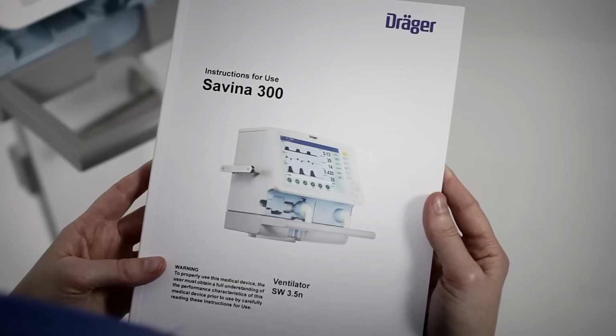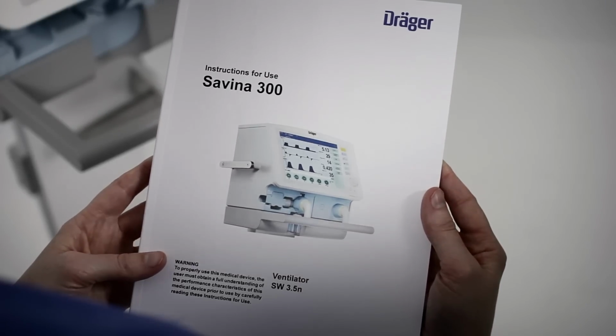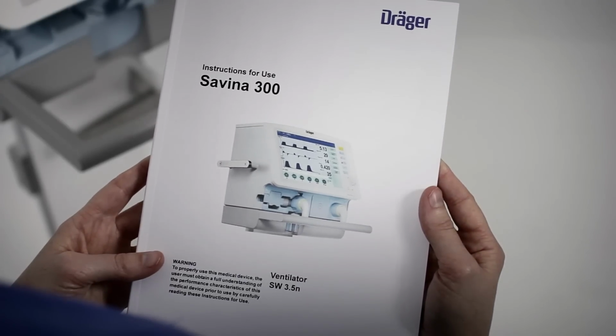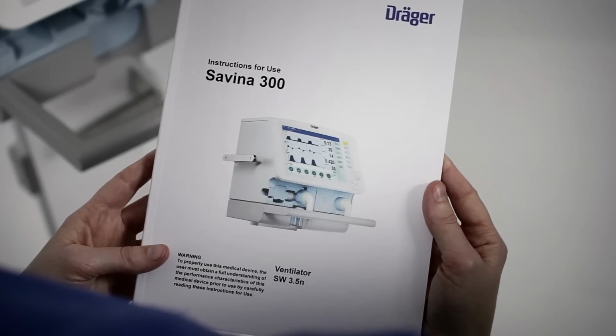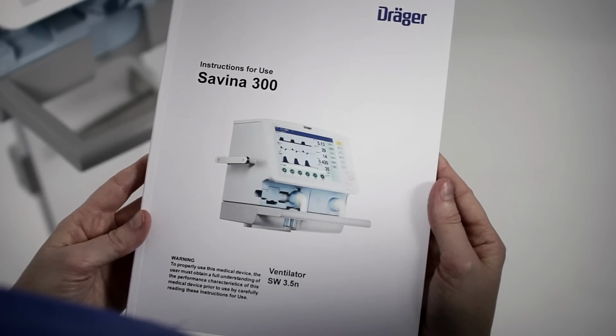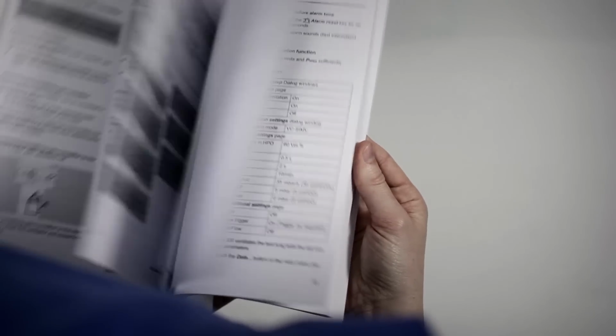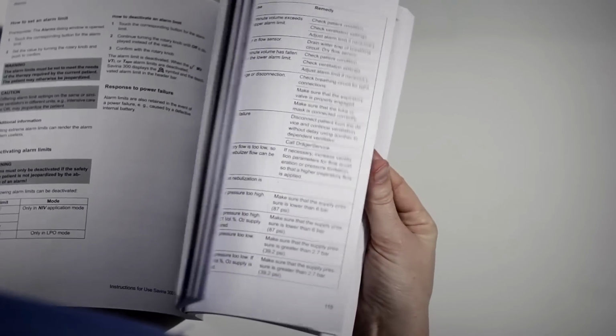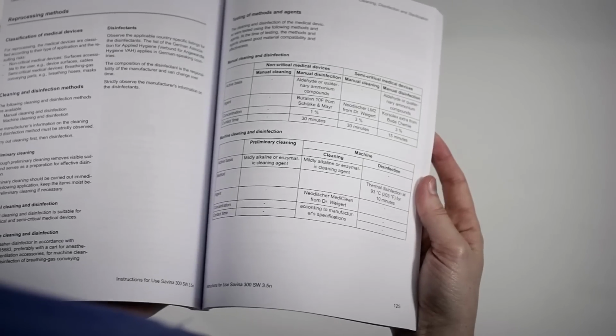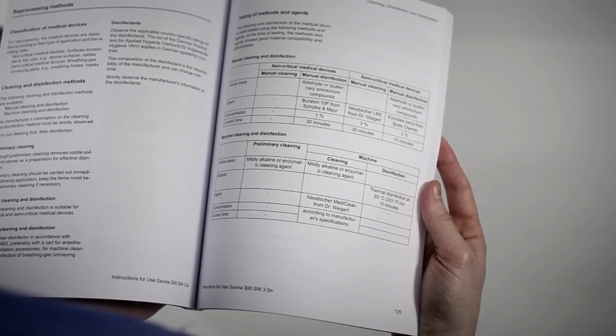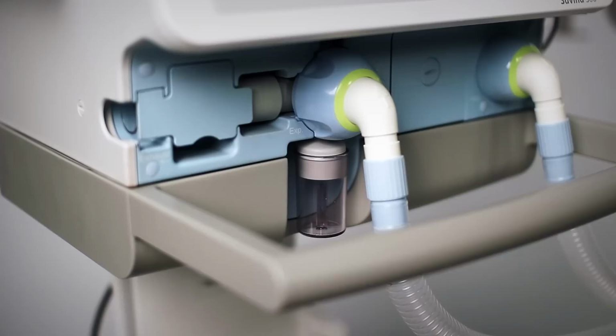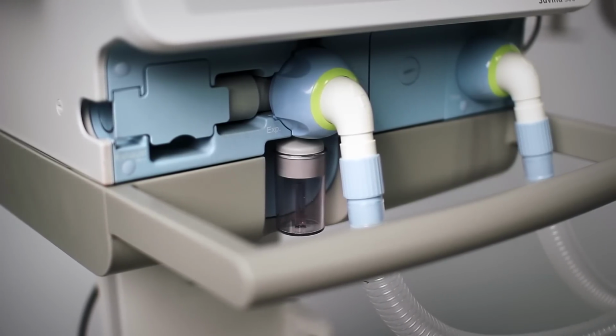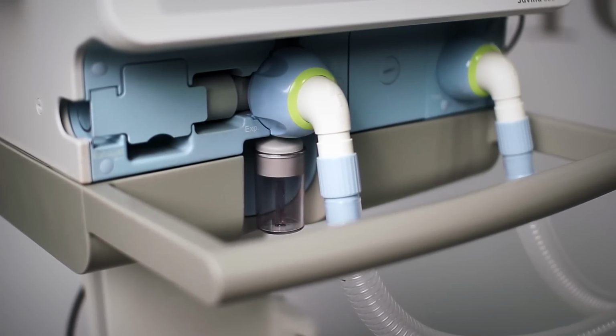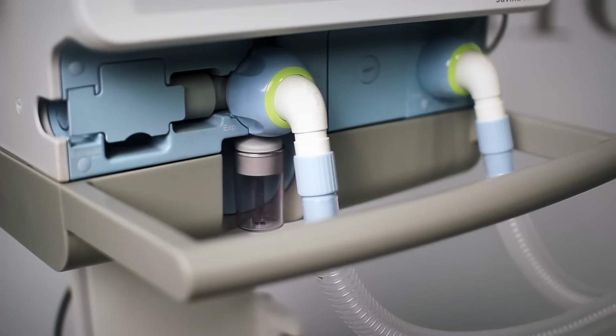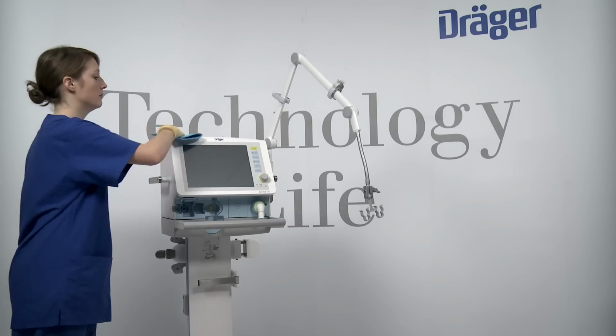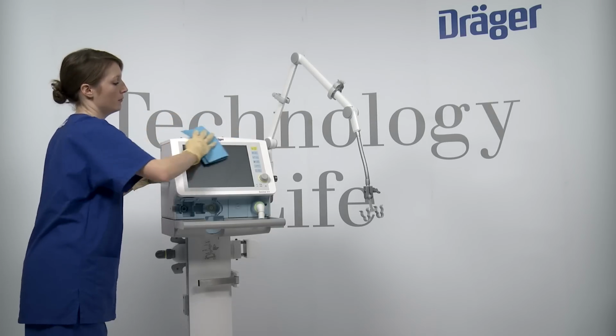If a medication nebulizer was used, dismantle it in accordance with the corresponding instructions for use and reprocess the components in accordance with the reprocessing list for semi-critical medical devices. Reprocess the breathing gas temperature sensor, the reusable CO2 sensor, the breathing hoses, the flow sensor, and the components of the expiratory valve in accordance with the reprocessing list for semi-critical medical devices. After cleaning and disinfecting, always dry the expiratory valve by means of hot steam sterilization at 134 degrees Celsius or 273.2 degrees Fahrenheit to ensure that all remaining liquid is dried completely in the interior areas.